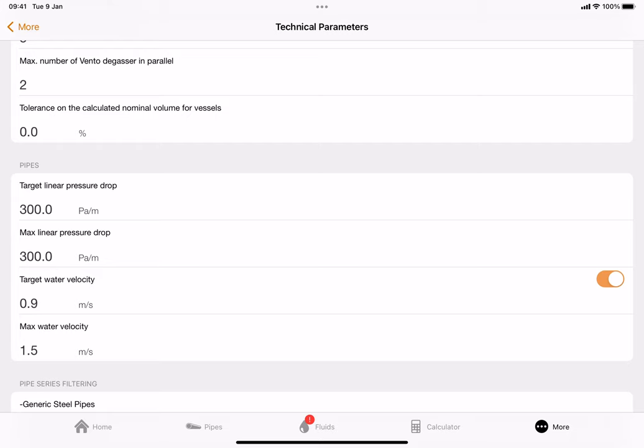So to get a decent understanding and allow you to make engineering decisions about this, I've set these at 0.9 to 1.5. Now what happens sometimes on the iOS app setup when you try to change it to 0.9 to 1.5 and then move down the page it goes back to a previous generic setting. If it does that, just click 'done' or click 'more' at the top to go back to the technical parameters page - it should save. Make sure the target water velocity of 0.9 is highlighted so that box is ticked and goes orange as you can see on the right-hand side of the page.